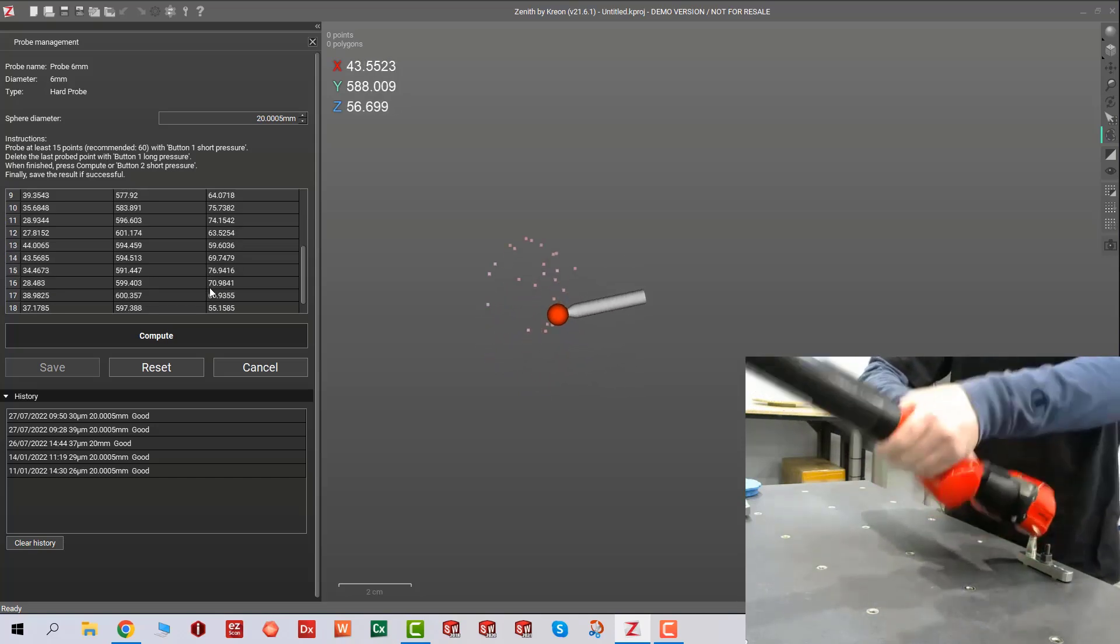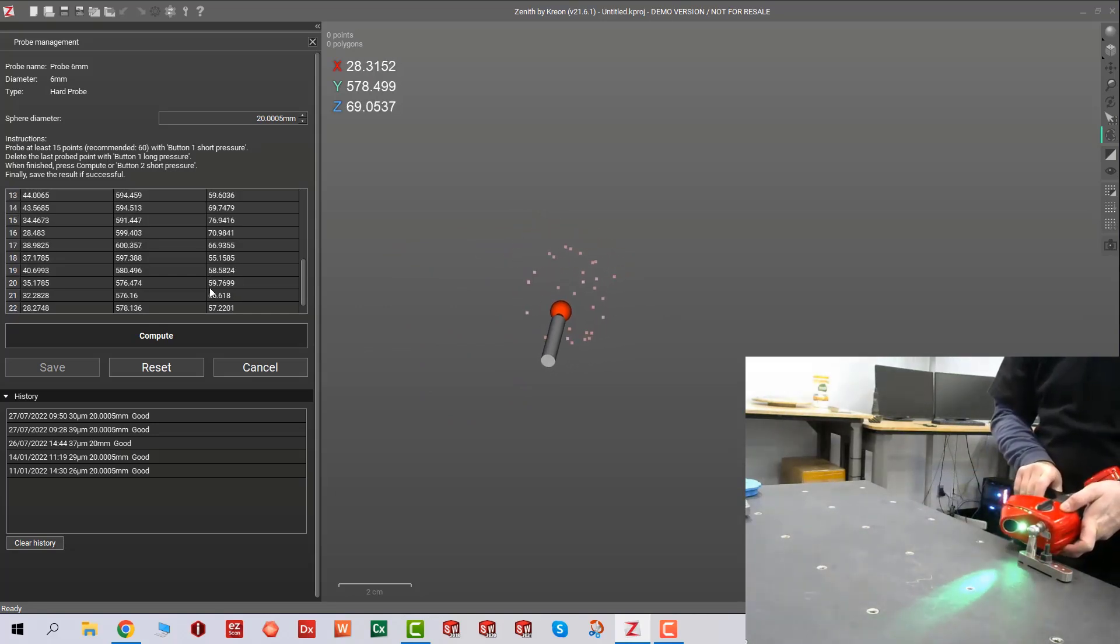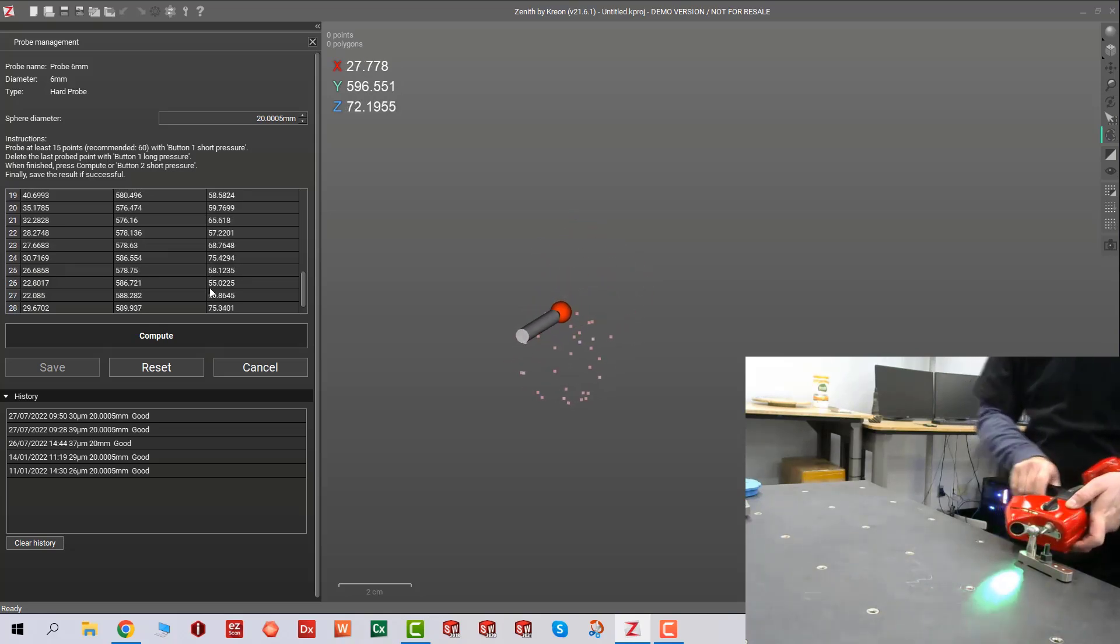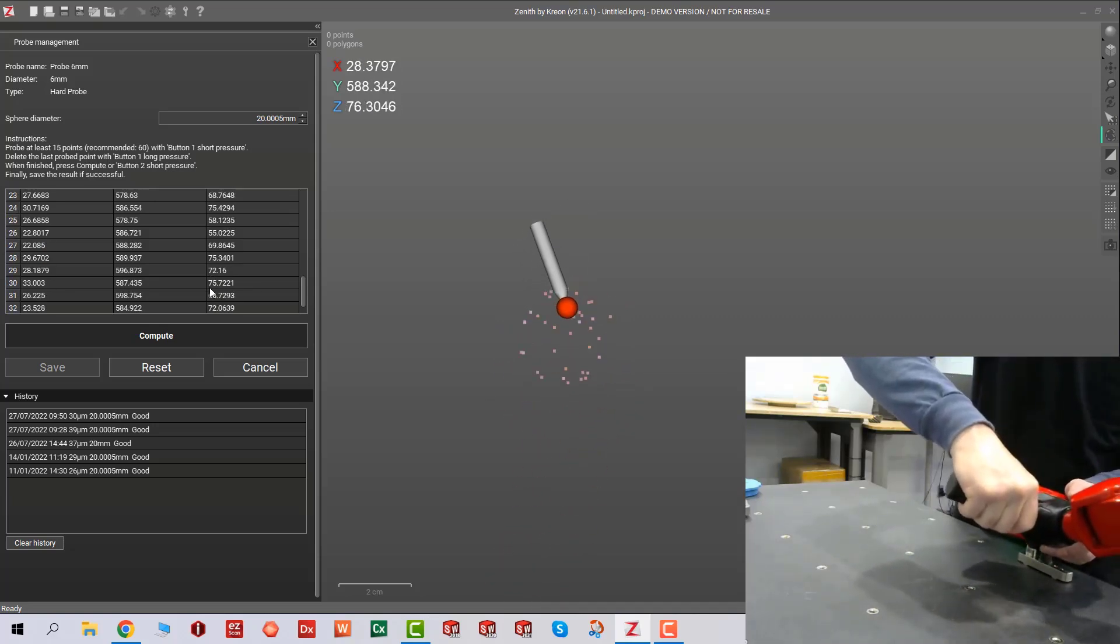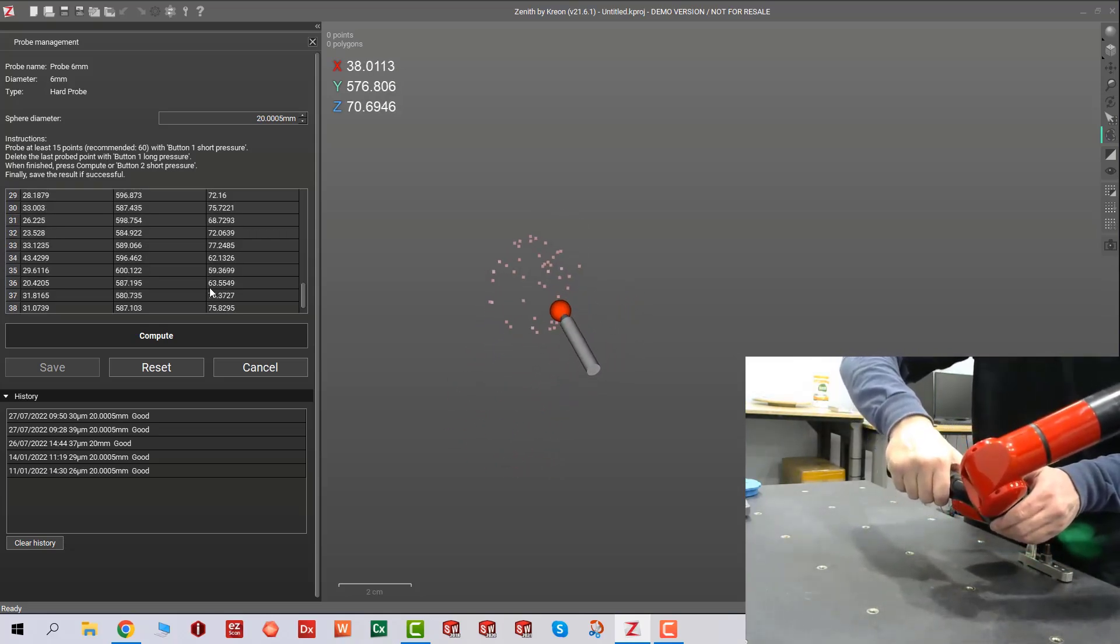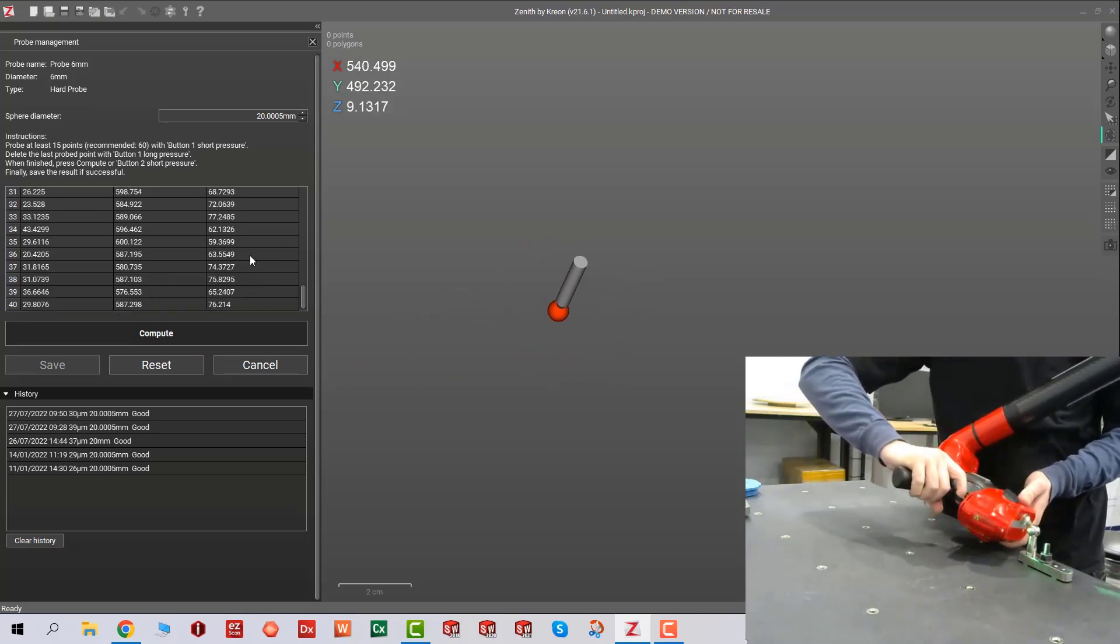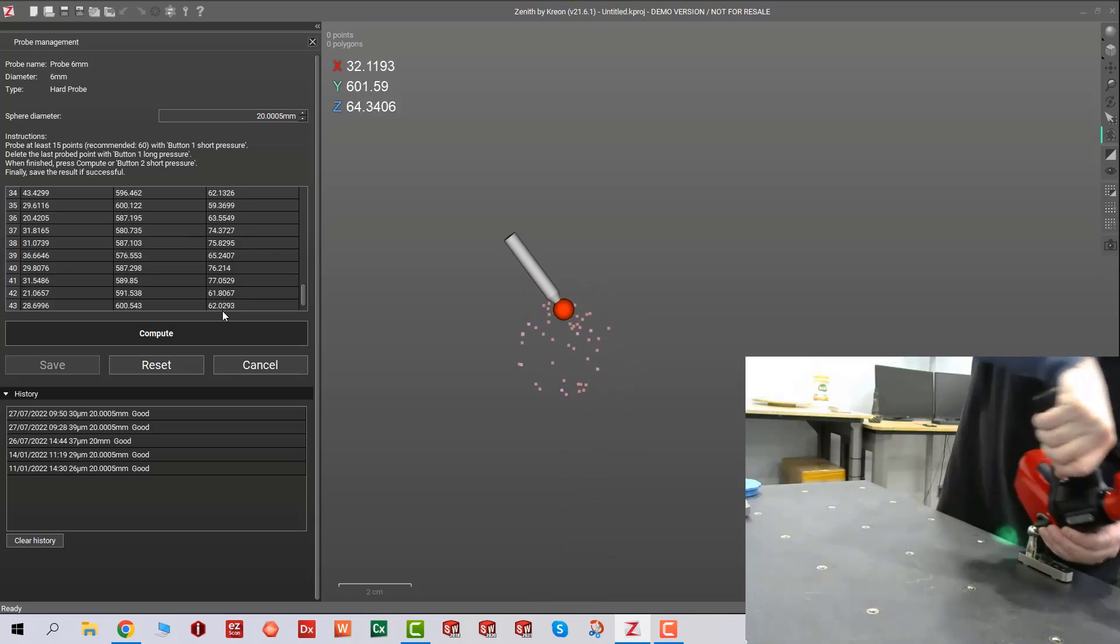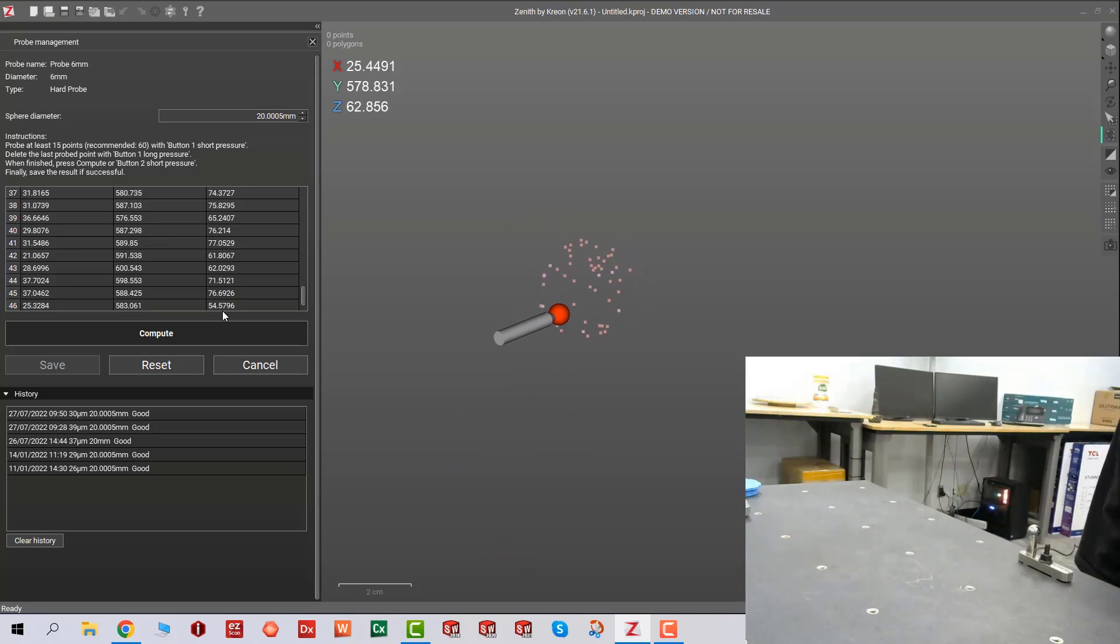If it's not secured, you might be collecting incorrect information. As I go around, I use this little tiny circle motion, collecting as much data as possible without moving my calibration sphere. Each time I change position, I stop, go back, and then start collecting again.